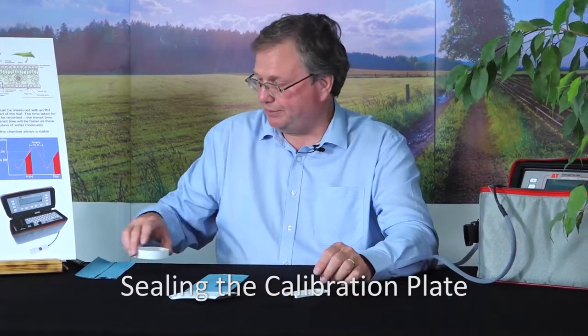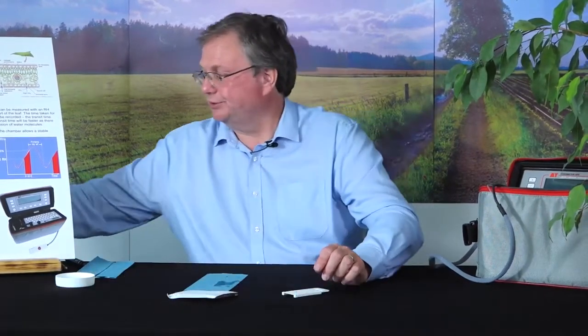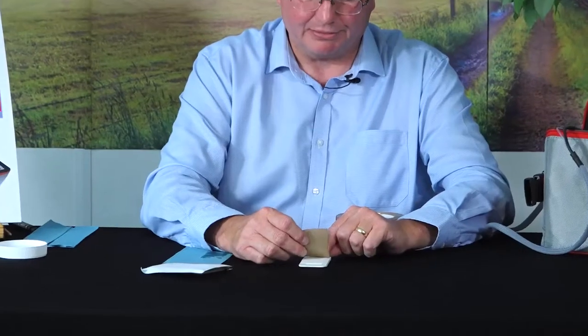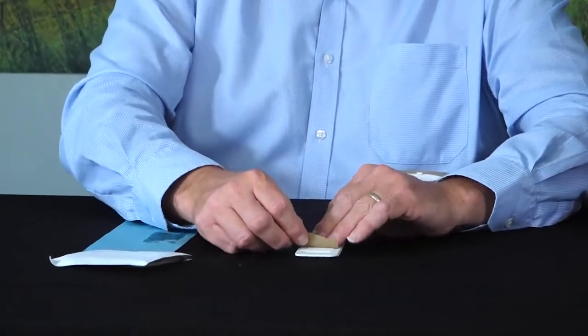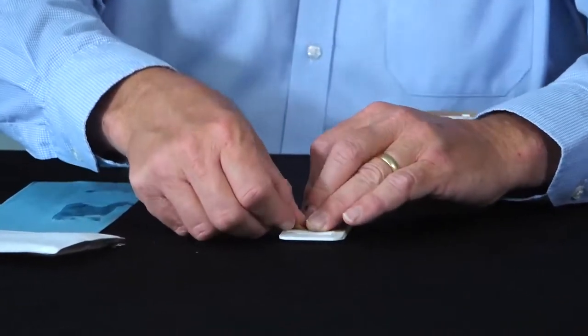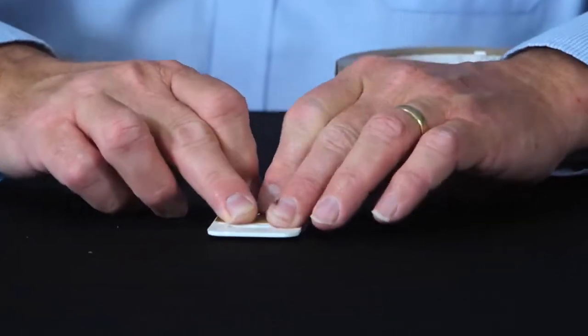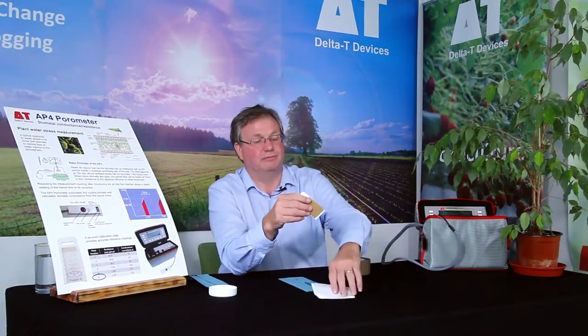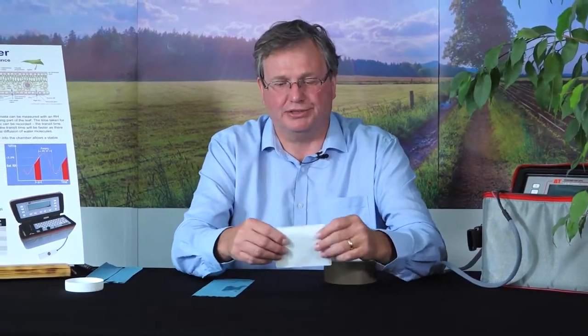To secure that in place, we'll use just normal brown parcel tape, which you need to apply carefully to make sure the filter paper is secured on the calibration plate and that you don't create any bubbles in the tape which will collect the water vapour that you generate. Once you've secured the filter paper, put the calibration plate back into the pouch and leave it for about an hour, and this allows the calibration plate to equilibrate to the humidity you've just generated with the paper. So put this to one side, and we can use this for calibrating the machine next.